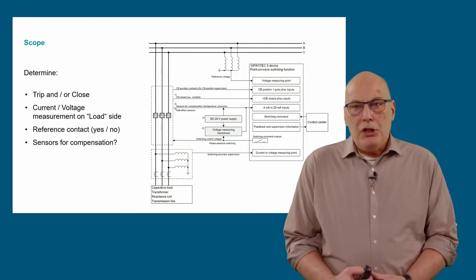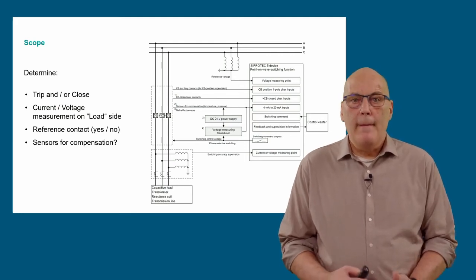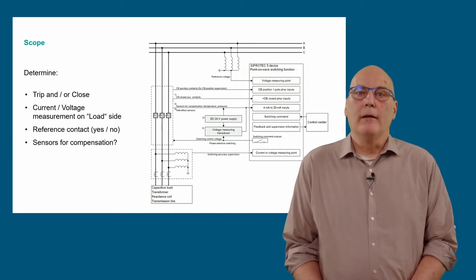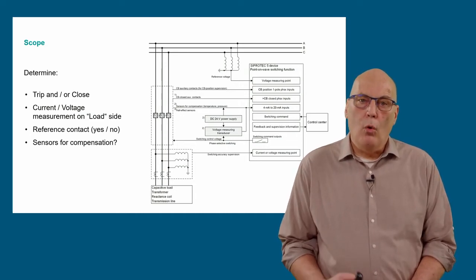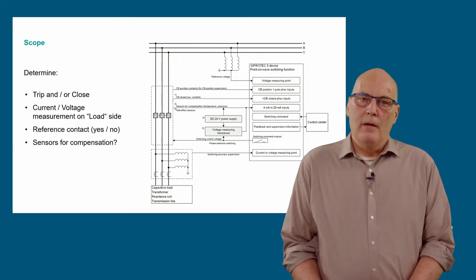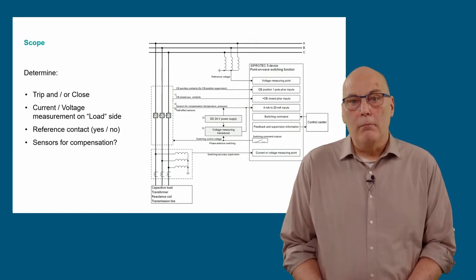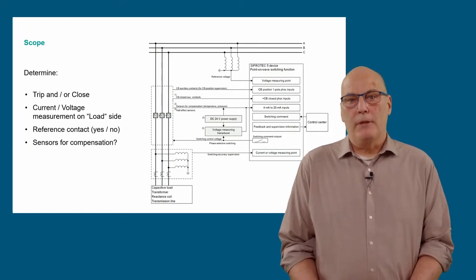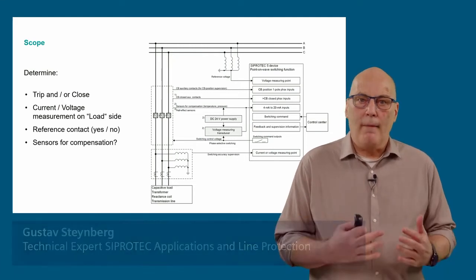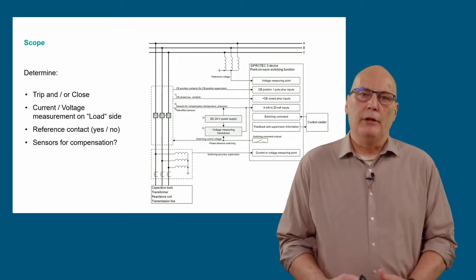The reference voltage used prior to switching by the point-on-wave function is on the source side of the circuit breaker — typically a voltage transformer connected to the bus bar. In applications with multiple bus bars, all voltage transformers can be connected to the device with an internal selection logic depending on the switching state of bus bar isolators. It must also be checked whether the circuit breaker mechanical switching will be monitored with reference contact and transducer inputs or via auxiliary contacts connected to binary inputs. The use of sensors for temperature, control voltage, and hydraulic pressure must also be defined.